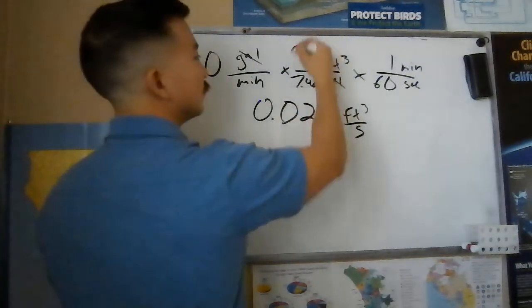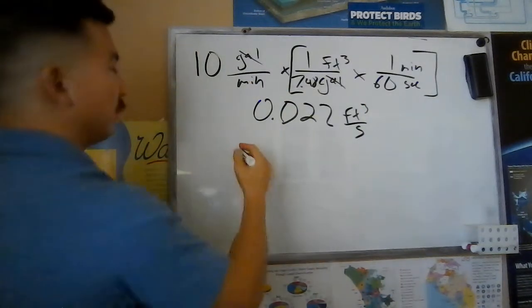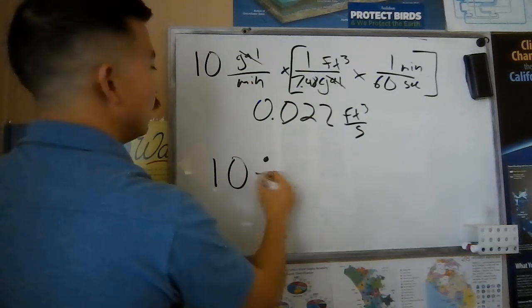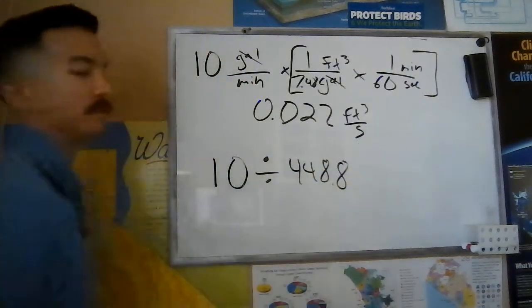Keeping in mind that if you're using the shortcut, the only difference here, the 7.48 times 60 is still going to give you the 448.8. But in this case, we're going to do 10 divided by 448.8 to get us 0.022 cubic feet per second.